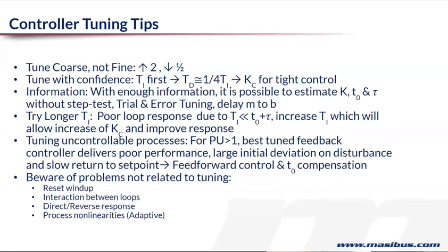So the only way is to first set your controller output limit. Most digital controllers have a limit setting, so you have to set that limit to where the valve delivers 100% flow. Then you prevent this reset windup.